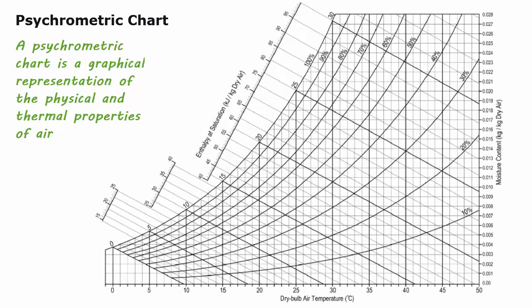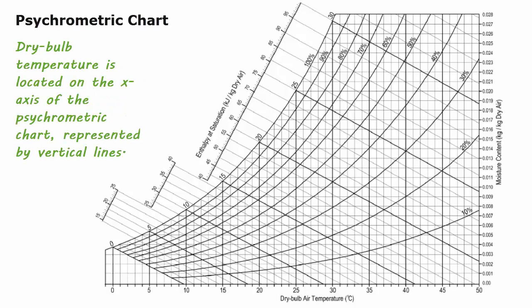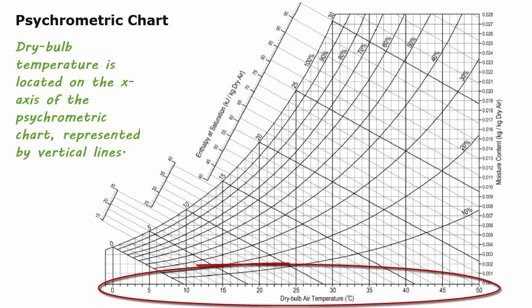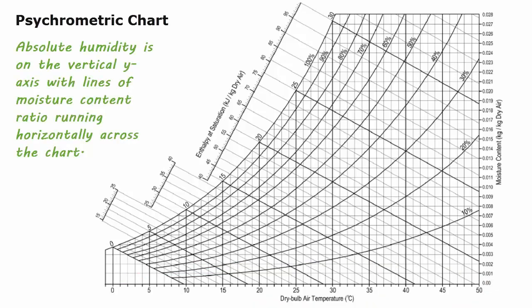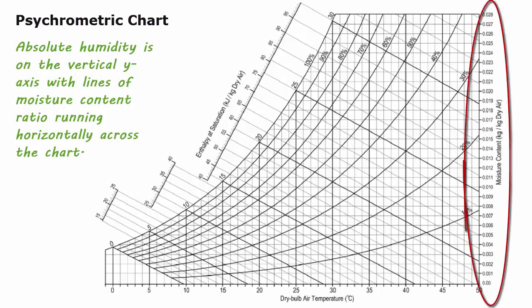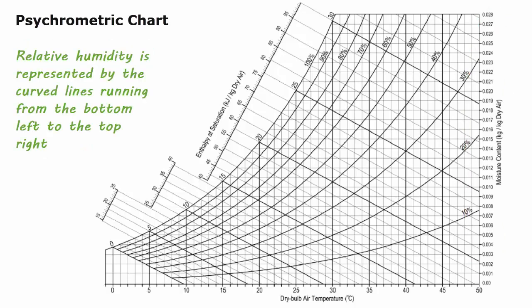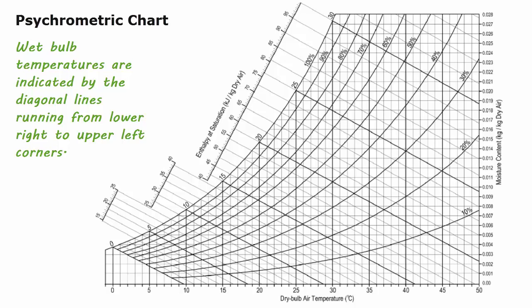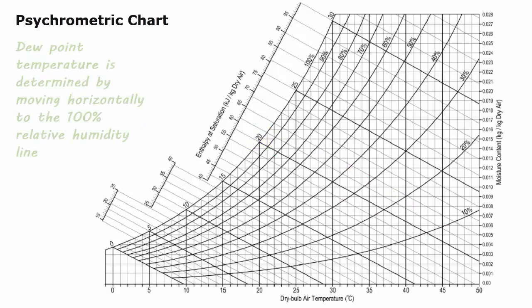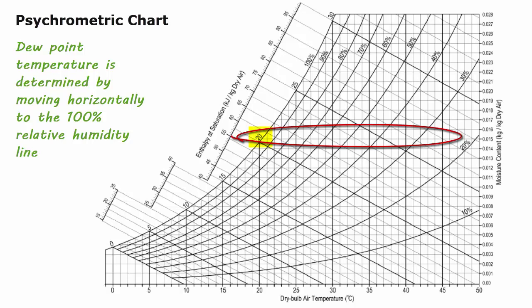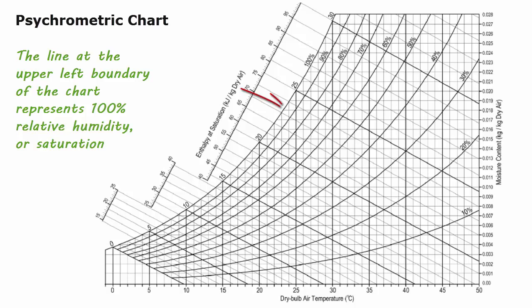A psychrometric chart is a graphical representation of the physical and thermal properties of air. Dry bulb temperature is located on the x-axis, represented by vertical lines. Absolute humidity is on the vertical y-axis with lines of moisture content ratio running horizontally. Relative humidity is represented by curved lines running from bottom left to top right. Wet bulb temperatures are indicated by diagonal lines running from lower right to upper left. Dew point temperature is determined by moving horizontally to the 100% relative humidity line, which forms the upper left boundary of the chart.